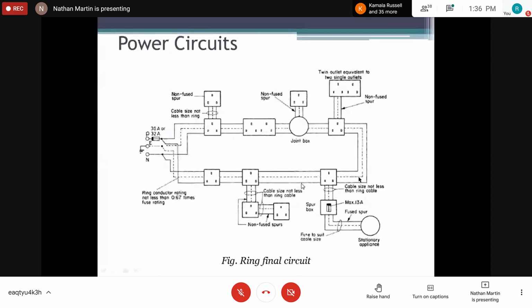So in a sensitive area where you have computers and so forth, this type of circuit will be more beneficial than a radial circuit, right? And we can maximize the number of circuits that are placed on this type of connection. Just to elaborate, the branch circuits from here are known as spurs. So for this type of installation, you can have spur circuits. They can be either non-fused or fused. In this case, for your water heater circuit, you would have a switch outlet, and that switch outlet will control your water heater. That's one form of connecting these power circuits.